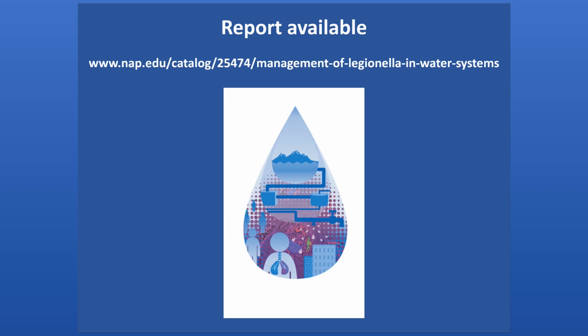The problem is that many plumbing codes and building contractors would never set a hot water heater at 60 degrees C, which is the same as 140 Fahrenheit—mainly due to scald concerns. So the committee has a table in the report that tries to demonstrate how one could balance scald risk along with Legionella growth potential risk. They felt these two temperatures, 60 and 55, can be balanced against each other. That's not to say that in a hospital setting with a vulnerable population, as you may have at a VA hospital, you wouldn't want to use thermal mixing valves to lower the temperature so you don't have 55 degrees C at the tap.